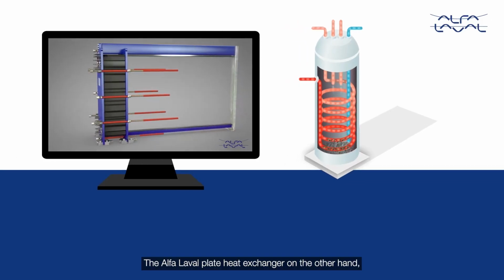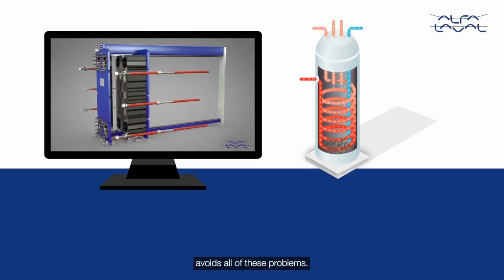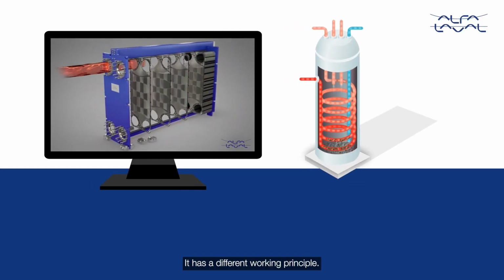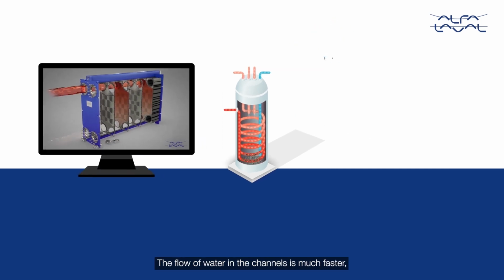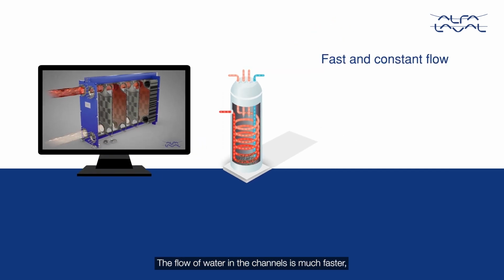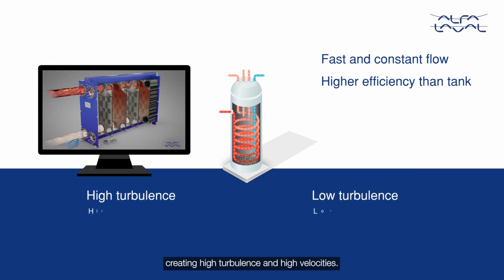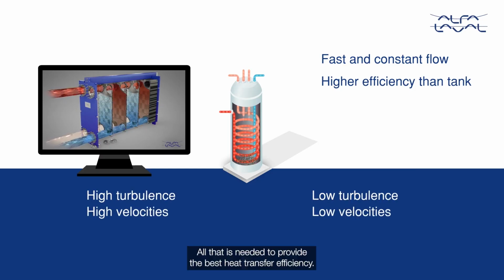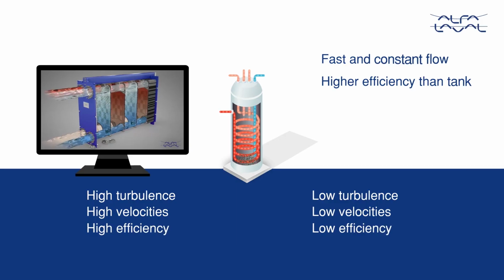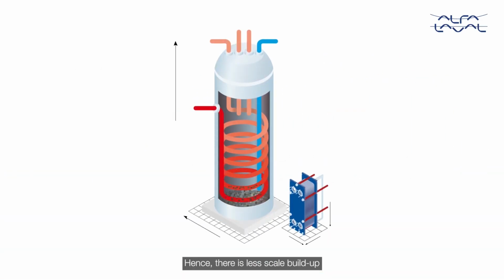The Alfa Laval plate heat exchanger, on the other hand, avoids all of these problems. It has a different working principle. The flow of water in the channels is much faster, creating high turbulence and high velocities, all that is needed to provide the best heat transfer efficiency. Hence, there is less scale buildup, providing savings in fuel costs.